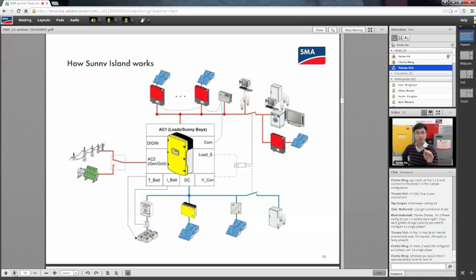You can have a generator as an external source. Say terrible weather for 4 days, batteries in a very deep state of charge, you basically have nothing else to use at all - now you can bring in the generator. Sunny Island has an internal system: when the state of charge drops to a certain percentage, which you can change, it will bring the generator in, charge the battery, supply the loads, until it charges back to a certain state of charge, then it will stop.